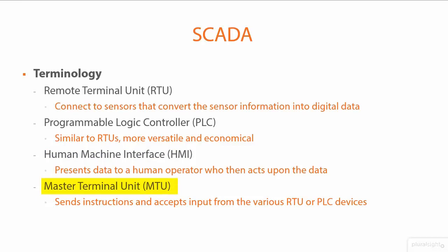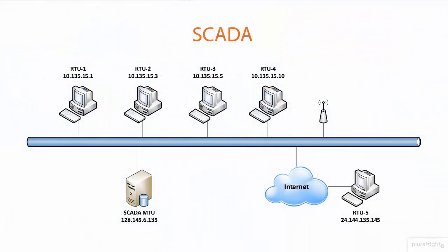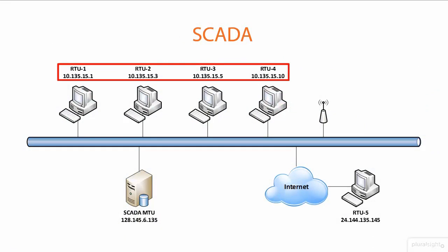The Master Terminal Unit, or MTU, sends information and instructions to the RTU or PLC and also receives information back, aggregating all of it. An example of what a SCADA environment might look like: you have a master control area or control center with screens from different systems — whether it's a nuclear power plant, water treatment facility, electrical grid, or sewage system. The PLCs and RTUs are spread throughout the entire system, all reporting back to the MTU, with an operator managing and monitoring everything.